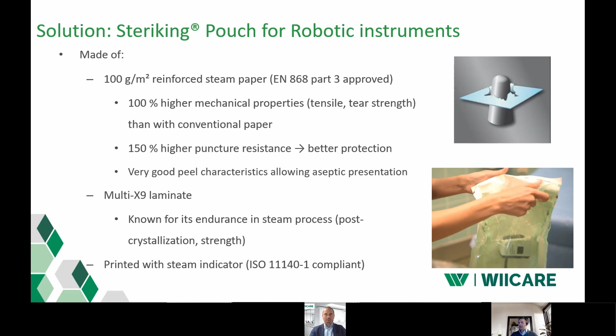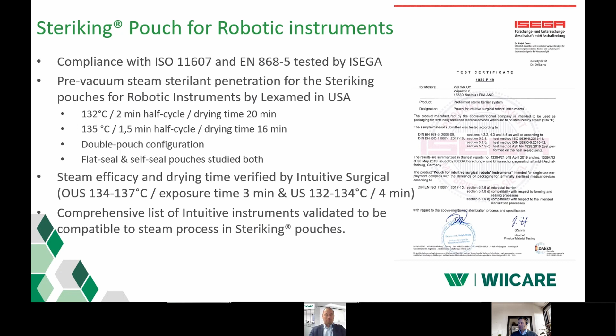We really have a lot of test data available on the pouch for robotic instruments, like compliance studies with ISO 11607 and EN 868 Part 5 tested by ISIGA in Germany. Then there is comprehensive data on steam sterilization in half-cycle methods in double-packed pouches tested by Lexamed in USA. In addition, Intuitive Surgical themselves have verified steam efficacy and drying time. All in all, there are more than 200 different Intuitive instruments available in the market.